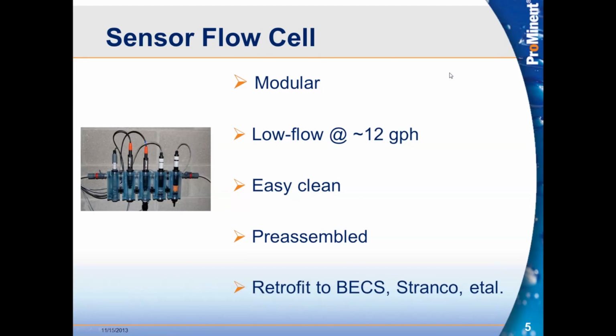A couple of minutes on the sensor flow cell. Our sensor flow cell has a couple of really important features that I think we need to talk about, and this goes back to sensor accuracy also. But up front, the sensor flow cell is modular by design, so that if somebody wants to expand or contract their flow cell assembly with different sensor packs, you can go ahead and do that and just add little blocks onto the BGMA sensor assembly.